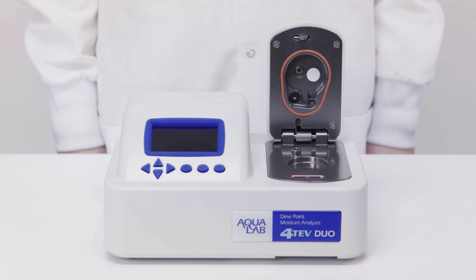The final option is the Series 4 DUO. The DUO uses a product-specific calibration to let you measure both water activity and moisture content on the same product simultaneously.